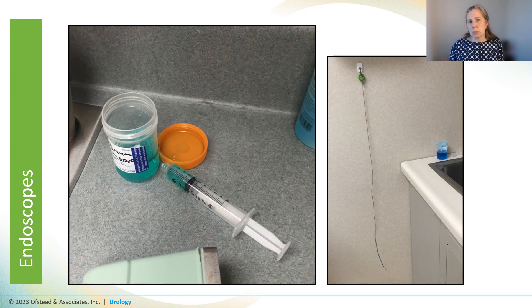This facility was washing their scopes in the hand hygiene sinks in the patient care room, squirting a string of undiluted enzymatic detergent on the scope and through the channel, and brushing it with a channel brush. That brush is hanging right on the wall next to the sink — very convenient — but the brush was never cleaned, disinfected, or sterilized between uses, which is pretty gross.